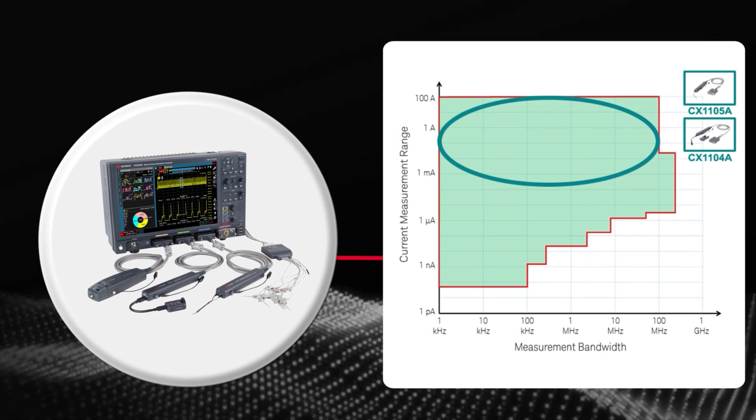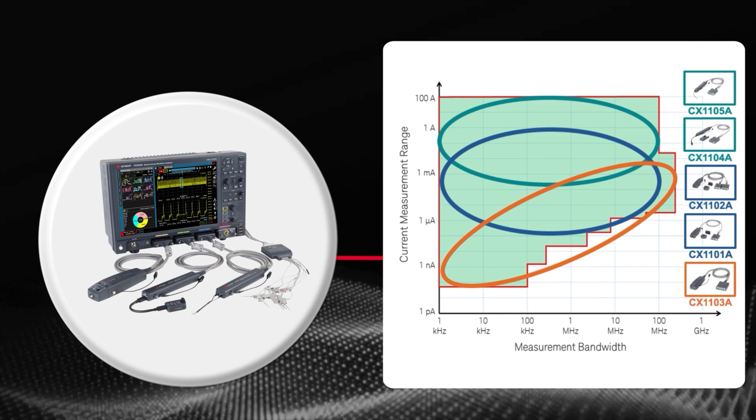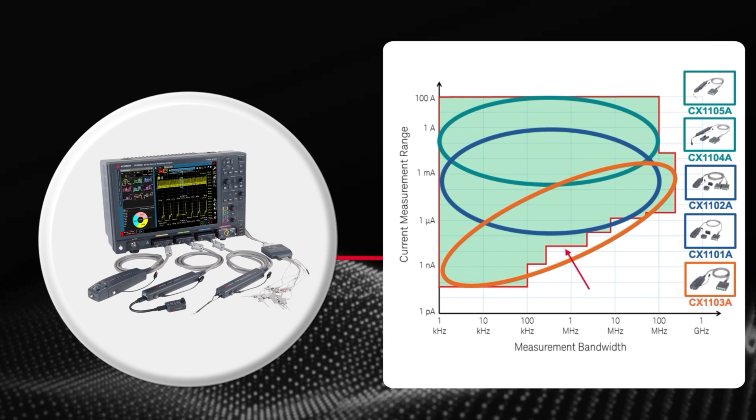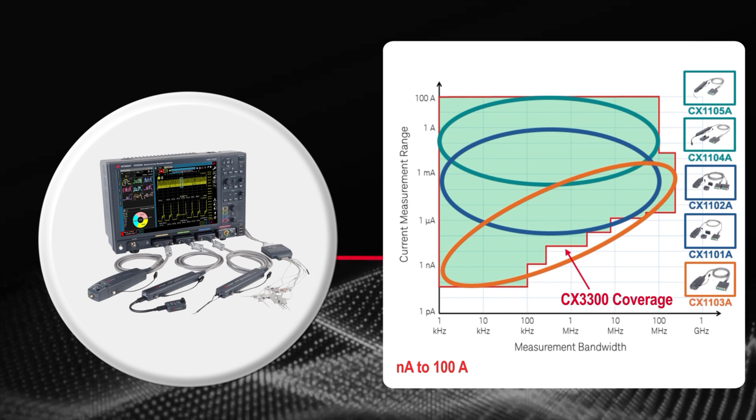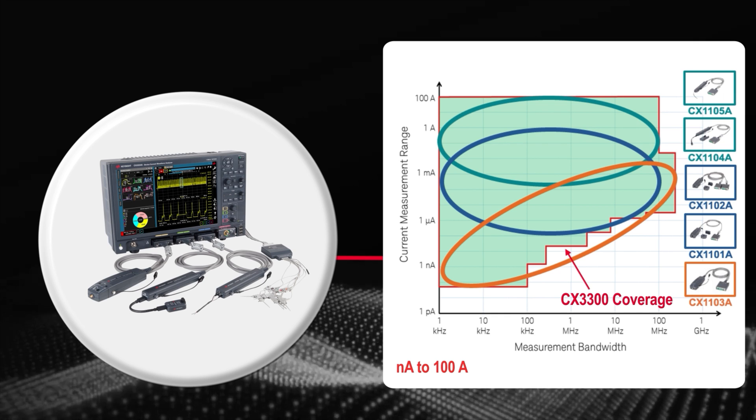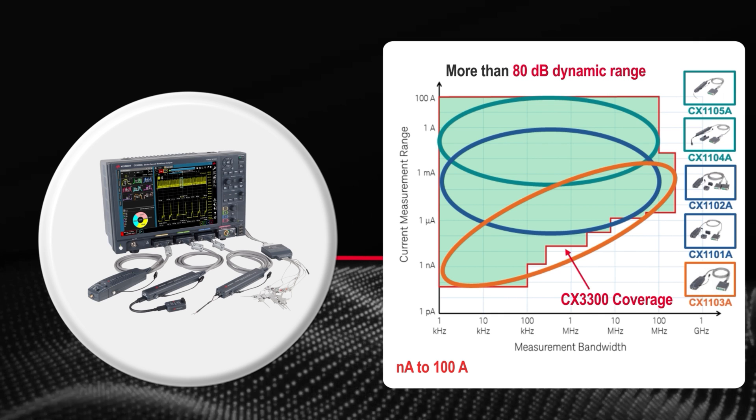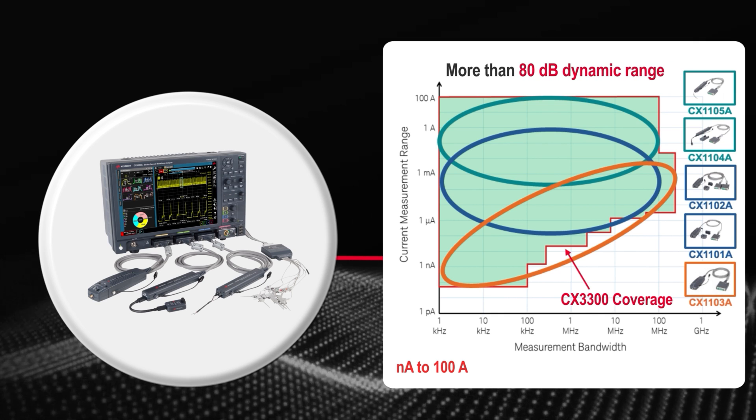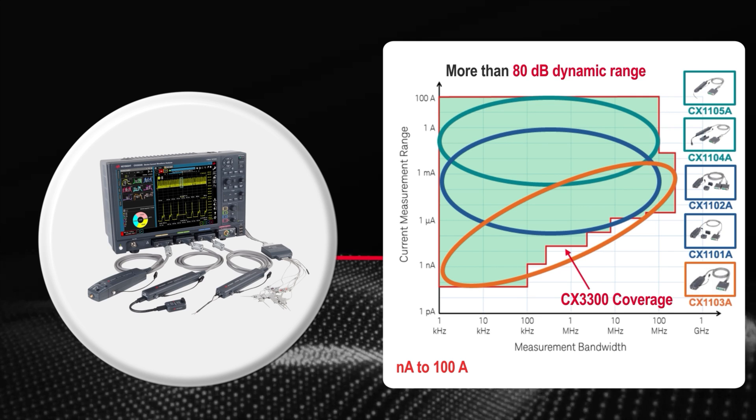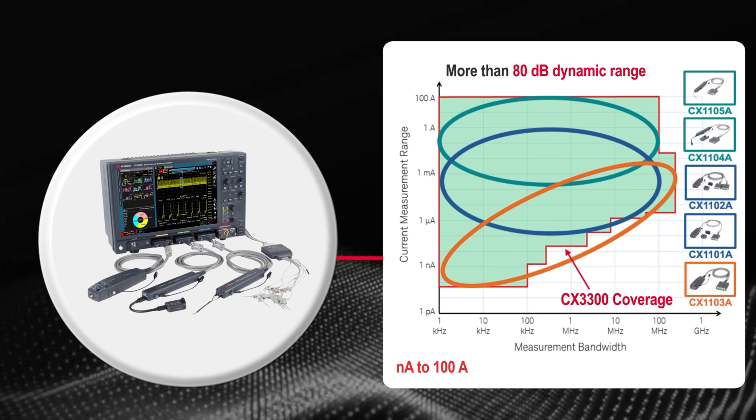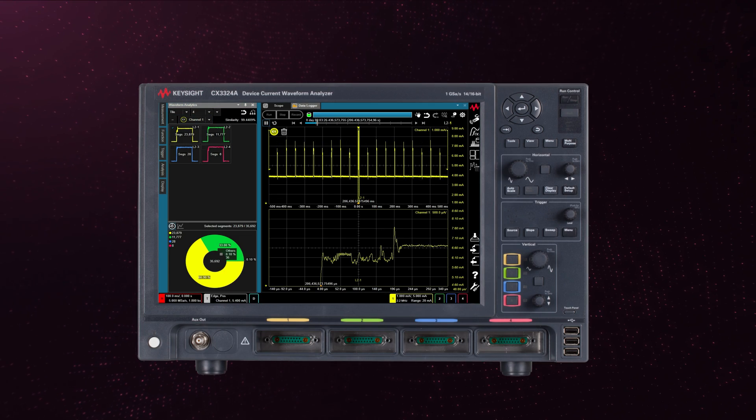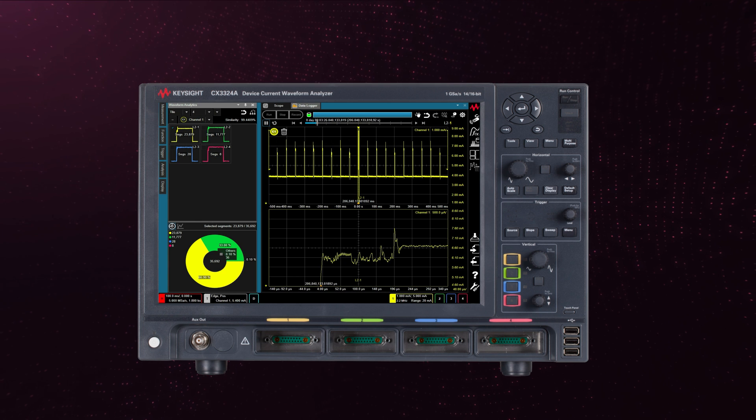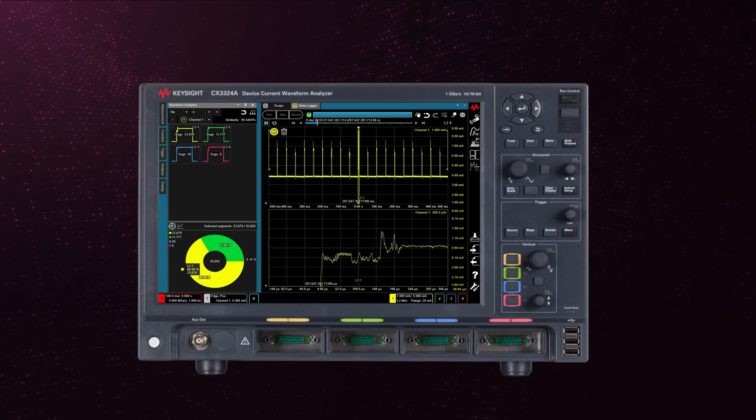In addition, the CX3300 covers a broad current measurement range from nano-amperes to 100 amperes with a dynamic range of more than 80 dBs using 4 current sensors and 1 differential sensor.